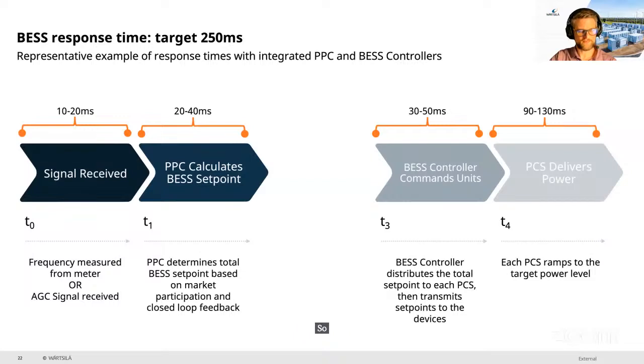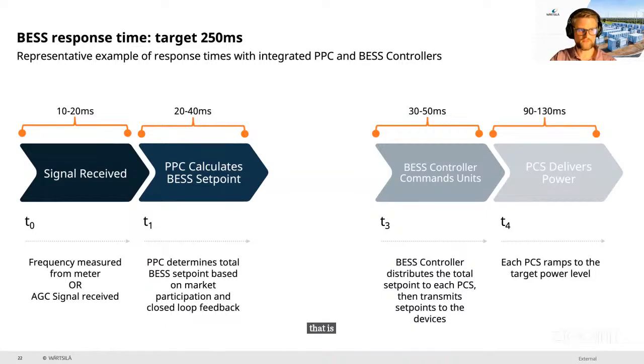So here's the same process, but in this case, we're looking at a plant that's using an integrated PPC and BESS controller solution. So in this case, there's only one set of hardware and software that is performing both the PPC layer and the BESS controller layer functions. So in this case, no external network interface is required to transmit that BESS target. So with all else being equal, removing just that extra hop between controllers brings our worst case closer to 240 milliseconds. Still a tight margin, but it is bringing you closer to 250.